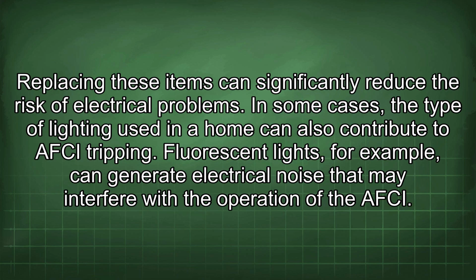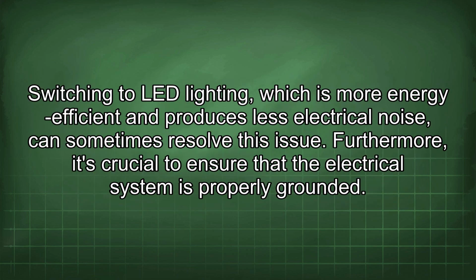In some cases, the type of lighting used in a home can also contribute to AFCI tripping. Fluorescent lights, for example, can generate electrical noise that may interfere with the operation of the AFCI. Switching to LED lighting, which is more energy efficient and produces less electrical noise, can sometimes resolve this issue.